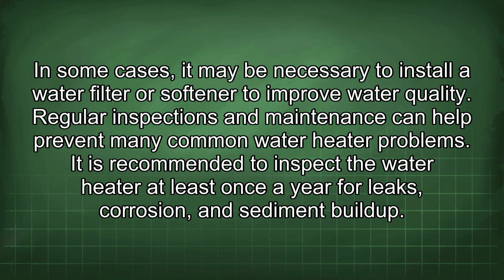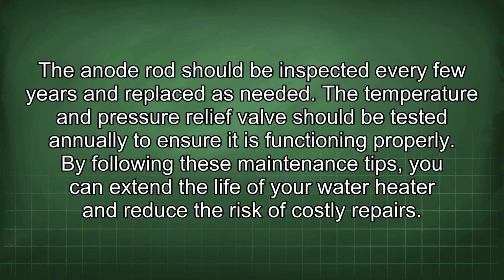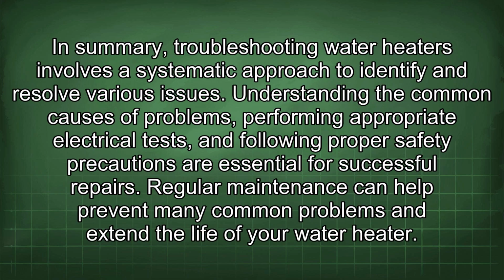It is recommended to inspect the water heater at least once a year for leaks, corrosion, and sediment buildup. The anode rod should be inspected every few years and replaced as needed. The temperature and pressure relief valve should be tested annually to ensure it is functioning properly. By following these maintenance tips, you can extend the life of your water heater and reduce the risk of costly repairs. In summary, troubleshooting water heaters involves a systematic approach to identify and resolve various issues.